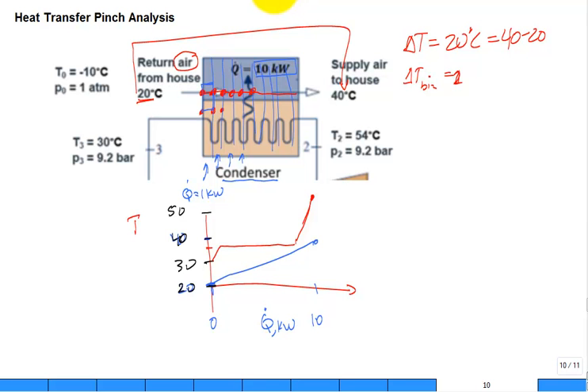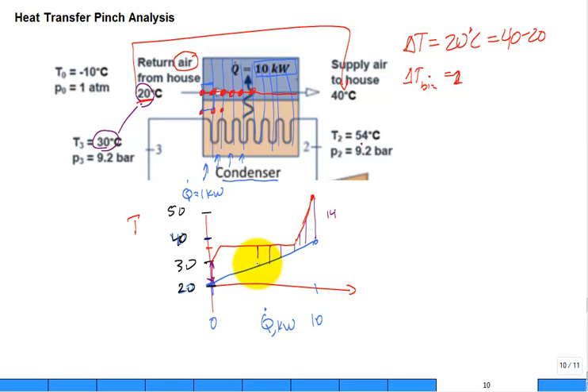What we do is check the delta T at each point. We can see it's not a uniform value everywhere — maybe it goes up and then goes back down, and the minimum delta T is somewhere in the middle. If the minimum is above a few degrees, that's great. But if the minimum gets to zero or below zero, then we have a problem. If it becomes negative, that heat exchanger just will not work.